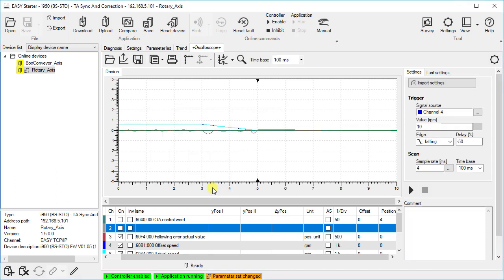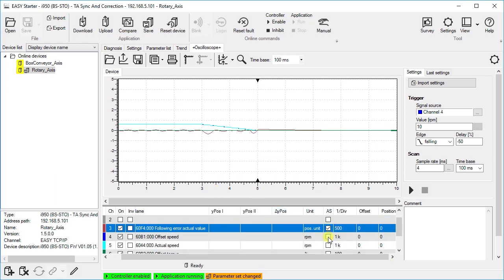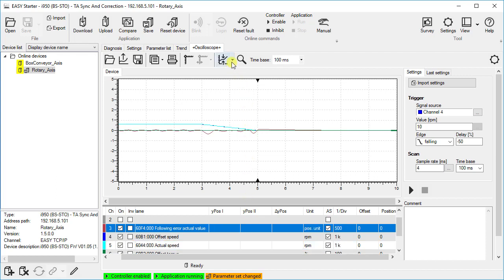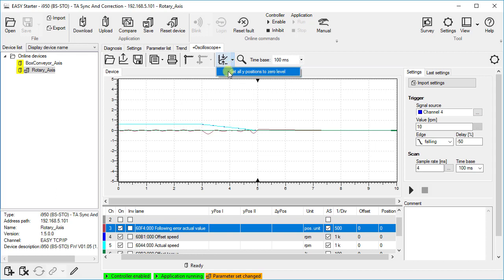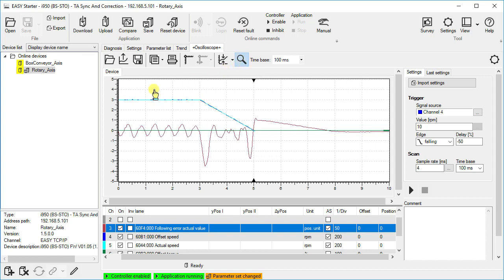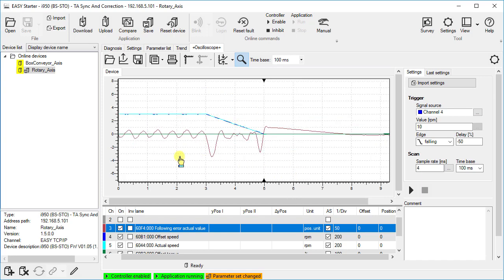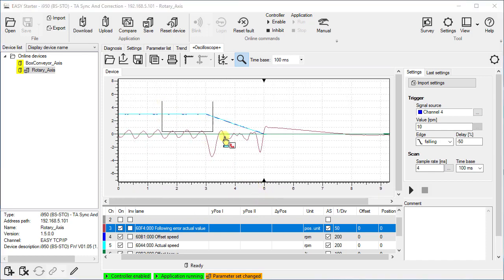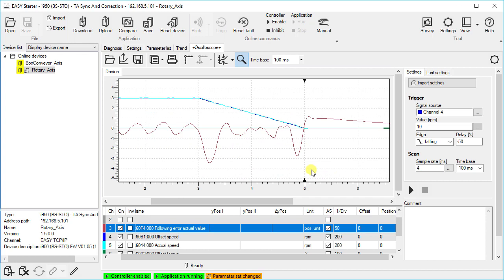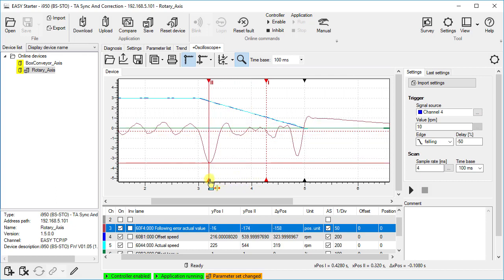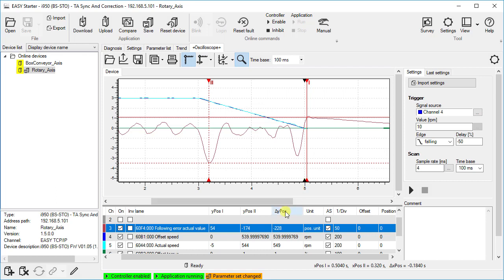For the first view it is helpful to use the auto scale function. We activate the checkbox in the column AS and use the oscilloscope toolbar. Click on scale curve automatically button or use the pull down option set all y position to zero level. Let us use the zoom function to display the curves more clearly. The blue curves represent the setpoint and actual speed and ramp down from 600 rpms to standstill. The following error between setpoint and actual value, the brown curve, increases briefly to approximate 200 position units during the dynamic deceleration process. This corresponds to approximate 1 degree difference at the motor shaft.